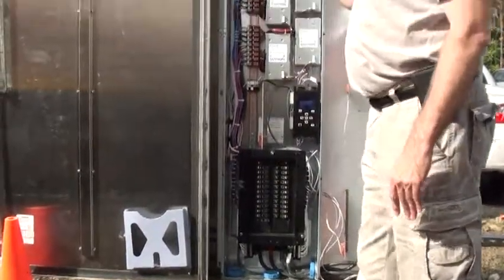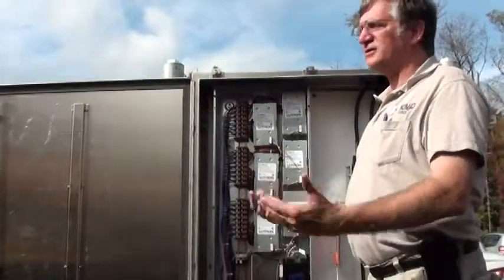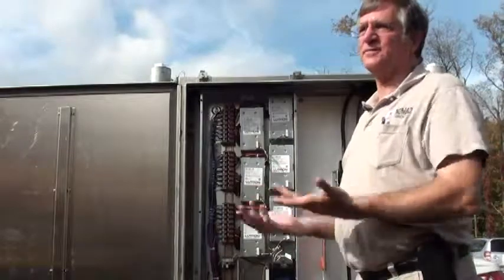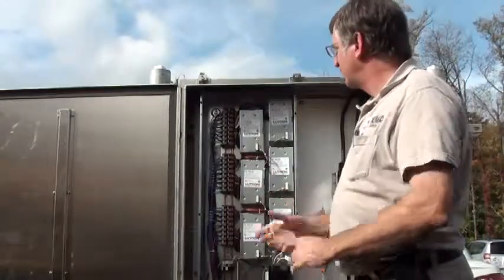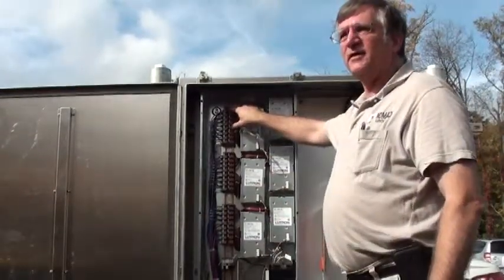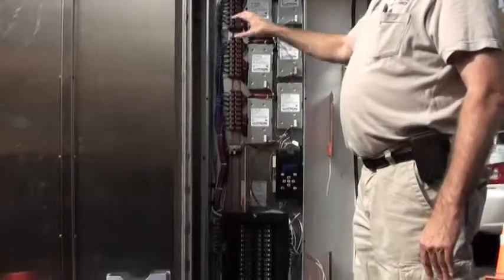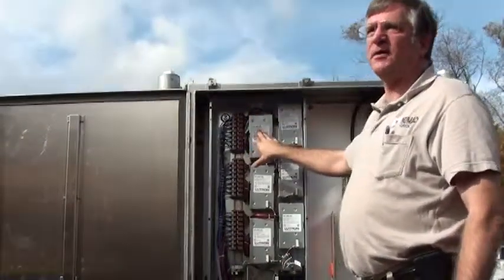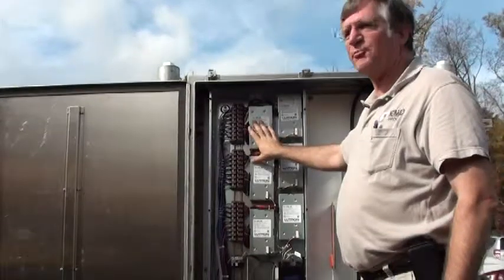If the breaker holds, pull your jumper out. The reason you're doing that is, it's a real world, right, something gets grounded or shorted or whatever, and the little jumper will take the current and pop the circuit breaker. If that thing is out and you do that, then you'll burn up your relay. So it's a self-protection piece.